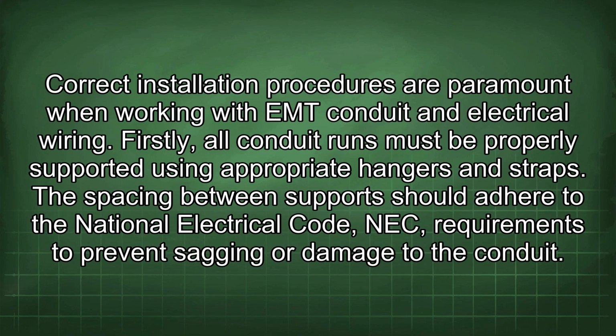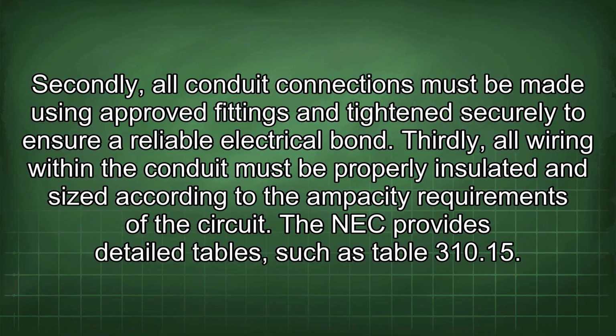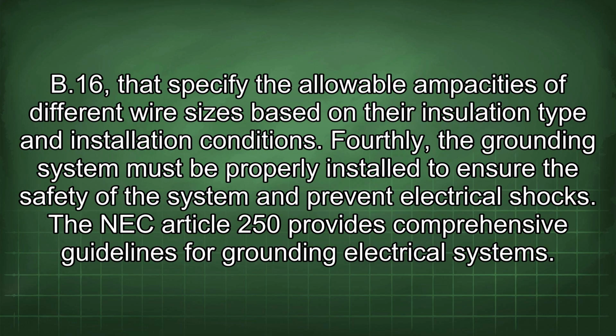Correct installation procedures are paramount when working with EMT conduits and electrical wiring. Firstly, all conduit runs must be properly supported using appropriate hangers and straps. The spacing between supports should adhere to the National Electrical Code (NEC) requirements to prevent sagging or damage to the conduit. Secondly, all conduit connections must be made using approved fittings and tightened securely to ensure a reliable electrical bond. Thirdly, all wiring within the conduit must be properly insulated and sized according to the ampacity requirements of the circuit. The NEC provides detailed tables, such as Table 310.15(B)(16), that specify the allowable ampacities of different wire sizes based on their insulation type and installation conditions.